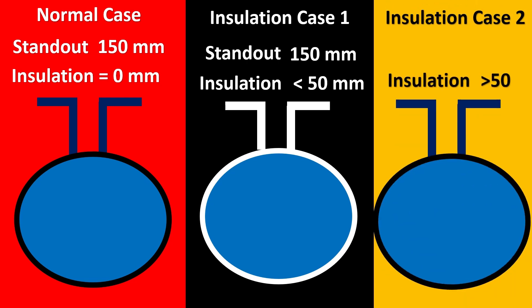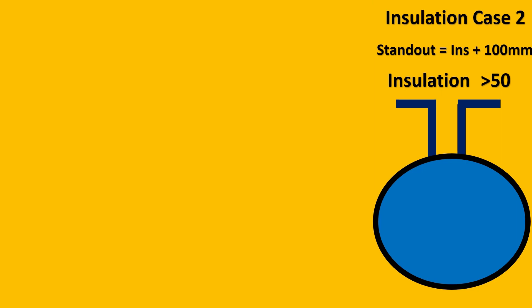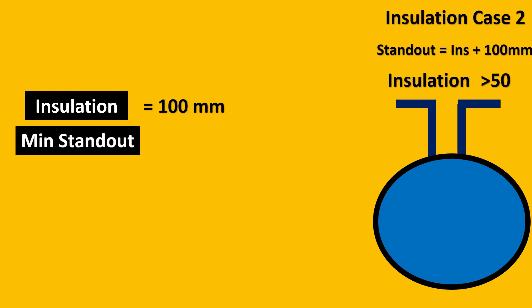But in insulation case 2, the insulation is actually greater than 50 mm. Here your standout has to be the insulation length plus 100 mm of clearance. This has to be your minimum standout. Let us calculate one case. So for example, your insulation is 100 mm and your minimum standout then has to be 100 mm which was the insulation plus 100 mm clearance. So minimum standout should at least be 200 mm.